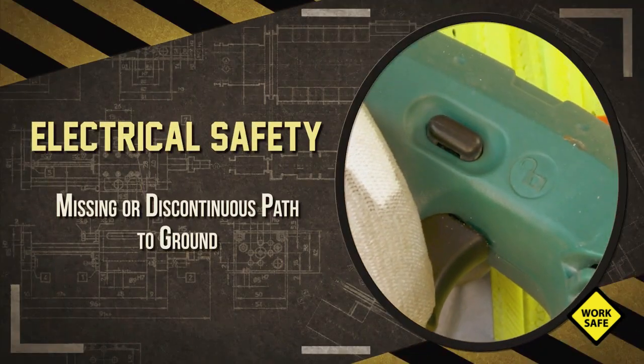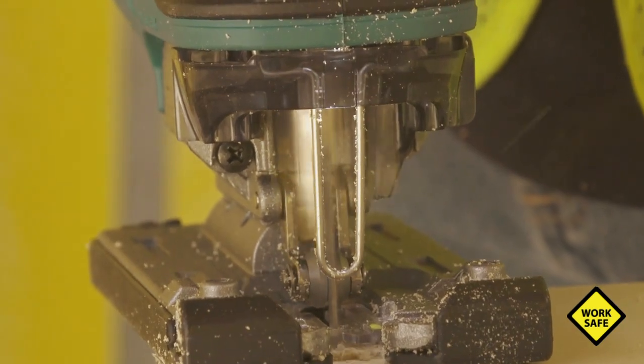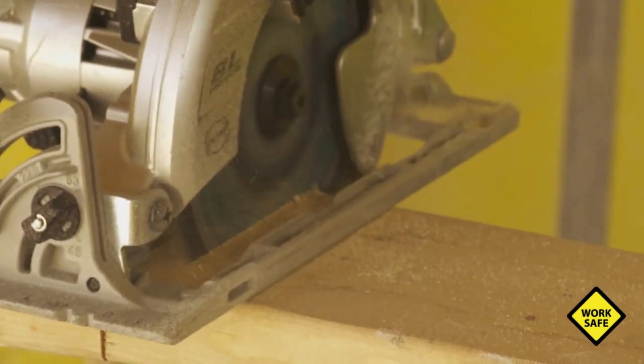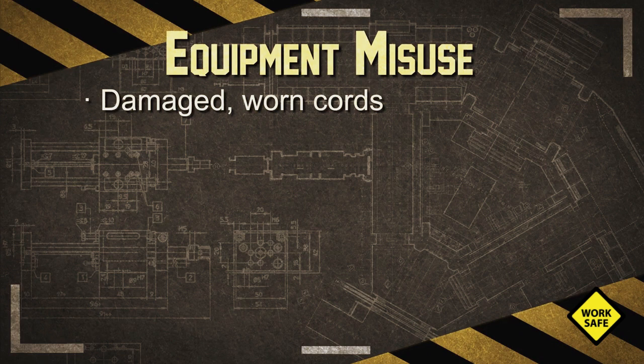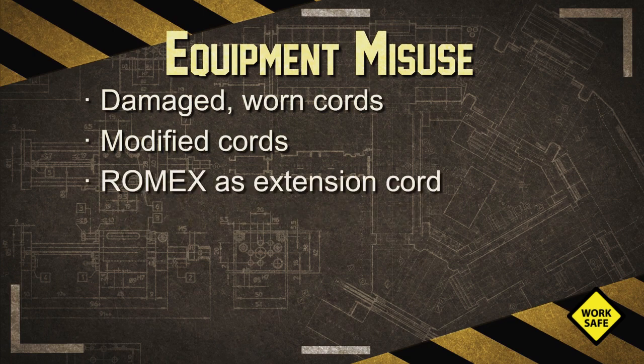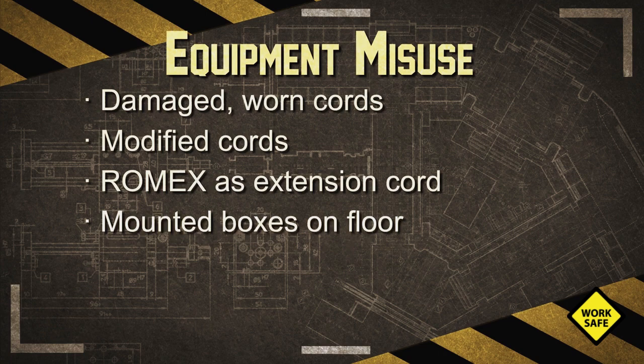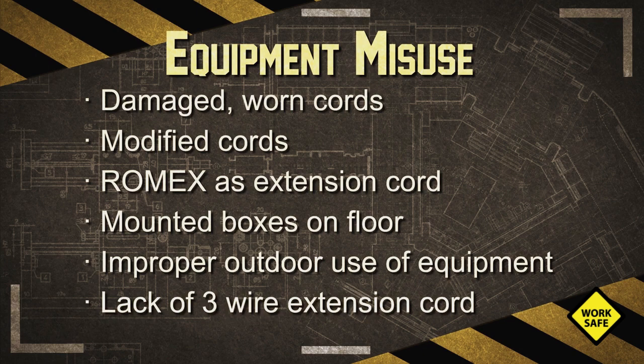Most electrical tools and equipment have safety features built into them by the manufacturer. However, if used in ways not intended by the manufacturer, operators no longer rely on these features. Examples of misuse include: using electrical cords or tools with worn or damaged insulation and exposed wires, using modified cords or tools missing faceplates, ground prongs, or insulation, fabricating extension cords with Romex wire, using junction boxes designed to be mounted with a power cord and placing them on the floor, using electrical equipment outdoors that is only designed for indoor use, and not using three-wire extension cords designed for hard or junior hard service typical for construction usage.